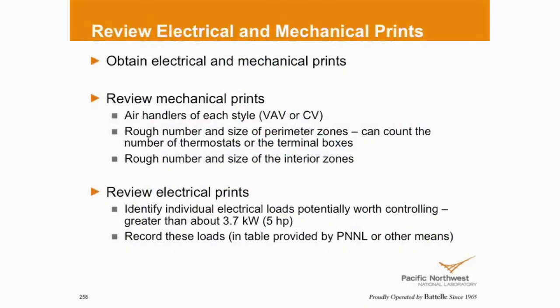So is the exhaust fan still running? It's now a legacy system. Was it shut down? If it was shut down, should it be removed and capped on the roof? Does it have an isolation damper? Is it an infiltration point for hot, humid air or cold air? That's one example of a legacy system. There's a lot of, I just demoed out a boiler. I got a stack going up through the roof. I got steam lines going here and there. Did I demo them all out? It's a penetration through my envelope, the stack. Did I get rid of it and seal it off? Those are what we're talking about when we're looking at mechanical prints, where there's opportunities to find more opportunities.